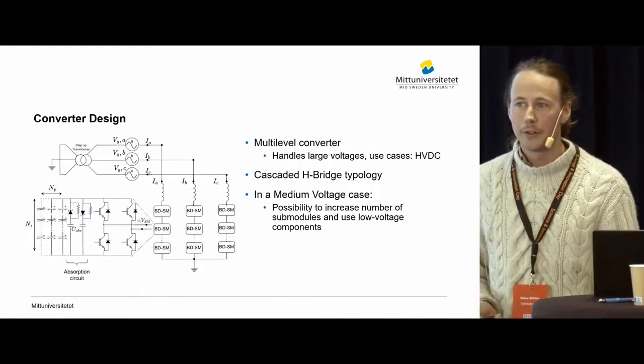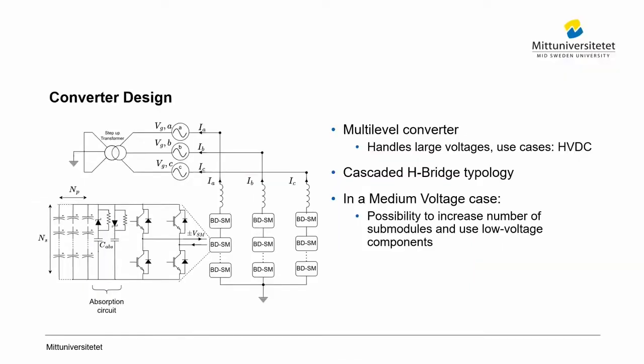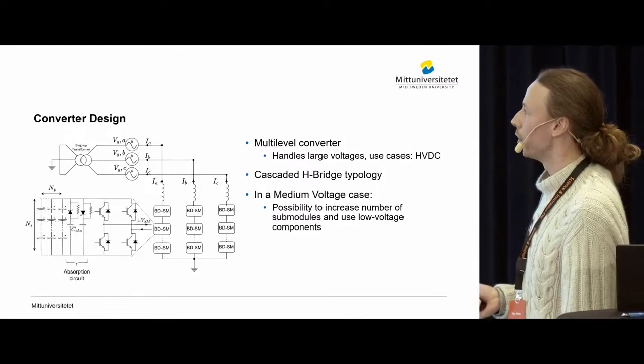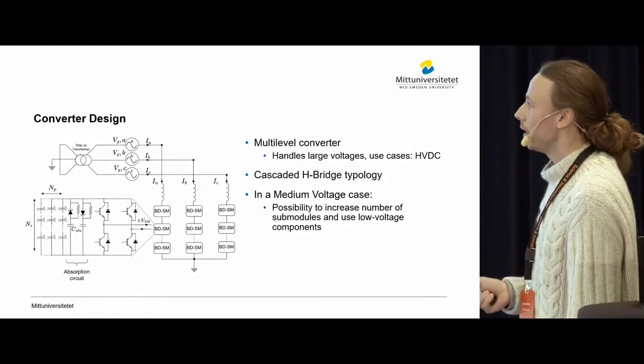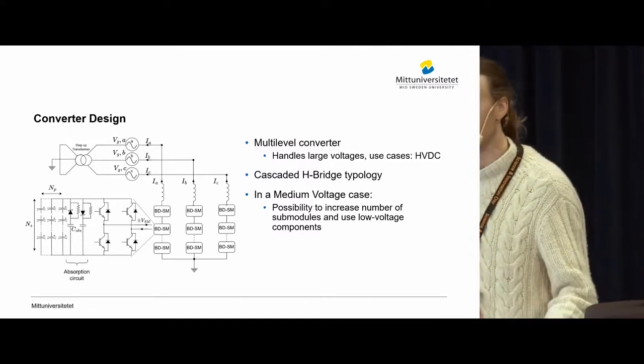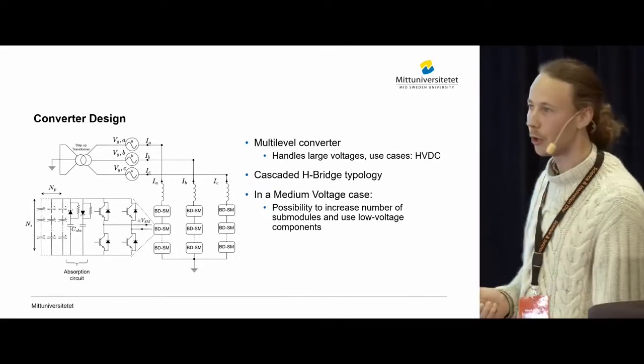I talked a little bit about converter design. One of the points of the research project is to develop a converter for this application. We've been looking at multi-level converters, which normally handle very large voltages, with use cases normally in HVDC. But in this medium voltage case we have 5 megawatts, we want to supply it to a 10 kilovolt connection point. We see there's a possibility to increase the number of sub-modules and use low voltage components, because the smart thing with the multi-level converter is that you can split up the voltage in one of these phase arms so that the semiconductor components in each sub-module only need to handle part of the total voltage. Here we want to integrate the supercapacitors in parallel or in series, and which configuration is part of our research project.